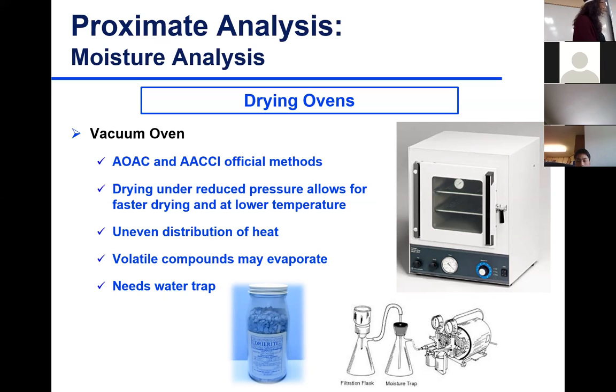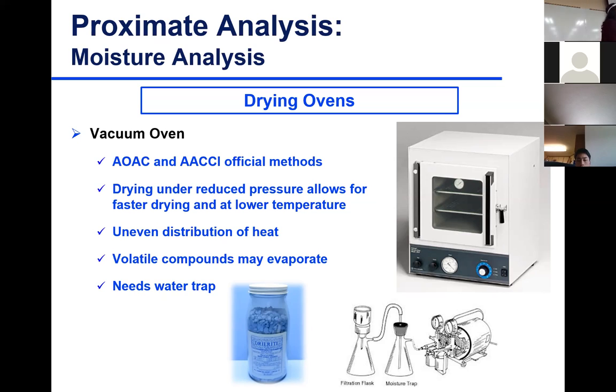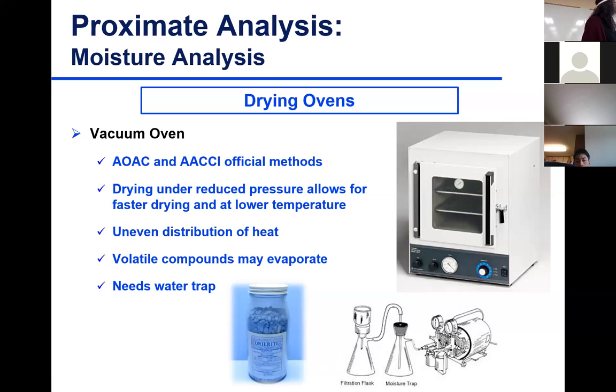An important feature of the vacuum oven you'll see in the lab is the water trap. You don't want moisture that evaporates to reach your vacuum pump. We call it a cold finger — basically a flask with desiccant in it. When the desiccant is dry it's blue; when saturated it turns pink or purple, indicating it needs replacement. The desiccant captures the water, preventing it from reaching the pump.